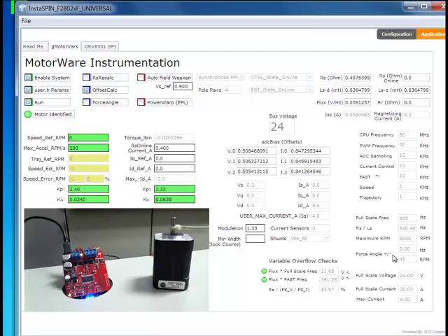With the settings that we have, which we talk about in the quick start guide, this ends up being 3 hertz, which is 45 RPMs for this motor. But again, we're going to turn this off so we can see the behavior at zero speed. At zero speed, we have these default settings for the speed controller, and this gain comes from the max current setting.